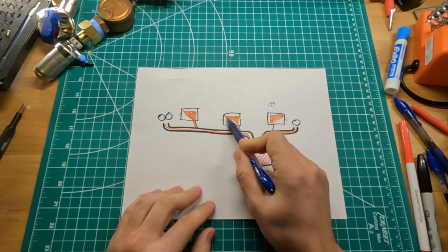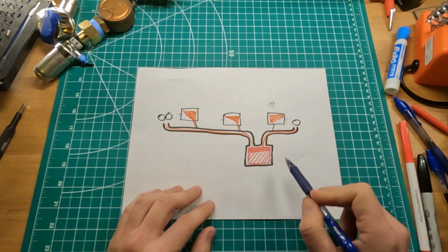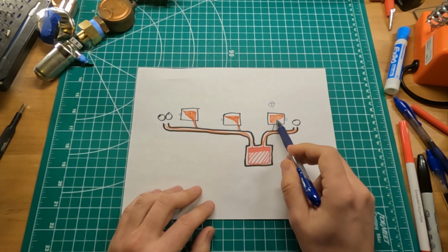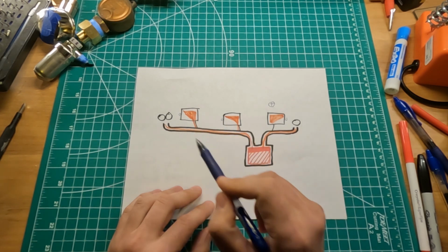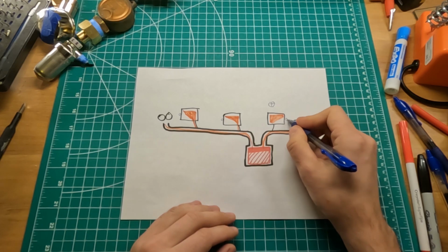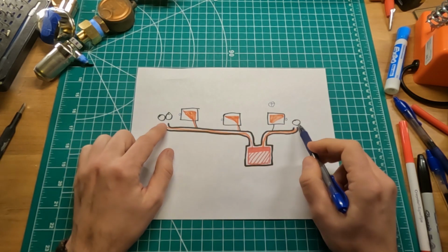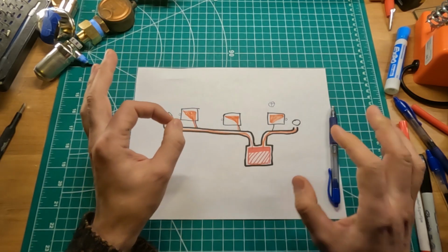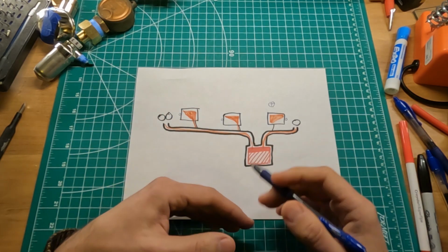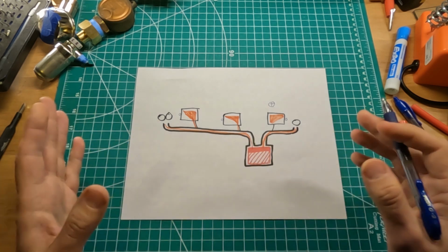So this fills up with steam quite quickly. This fills up with steam relatively quickly as well, and this might be filling up with steam more or less at the same time as this radiator is. So again, by controlling the sizes of those vents as well, because remember, main vents usually are quite big vents. So let's say that's why they put them here as the quite big circles.